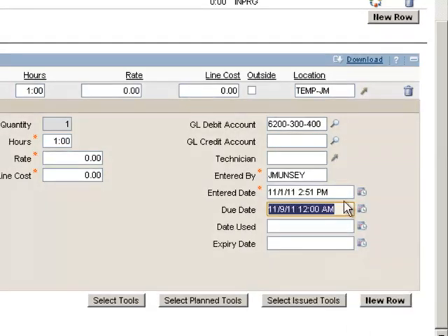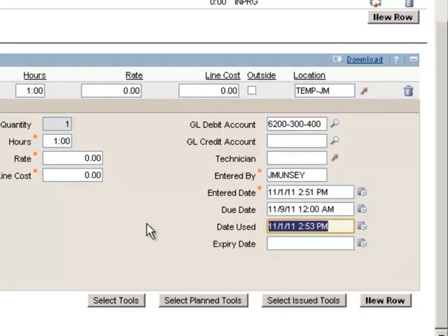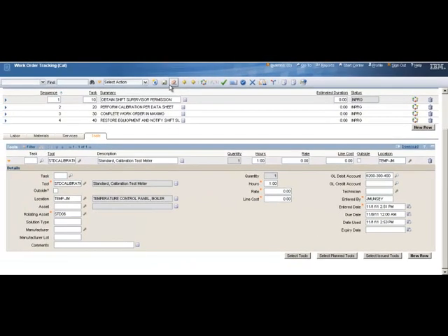So I'm going to make sure that my current one, based on a calibration due date on a sticker, is correct. And here's my date used, my date due for my instrument. And I want to record this. This is my indication that this calibration was performed with a valid standard. So I'm going to set that up, hit the save button, make sure everything's okay. And if it saves, you're good to go. And I've associated my calibration standard to my calibrated instrument now.